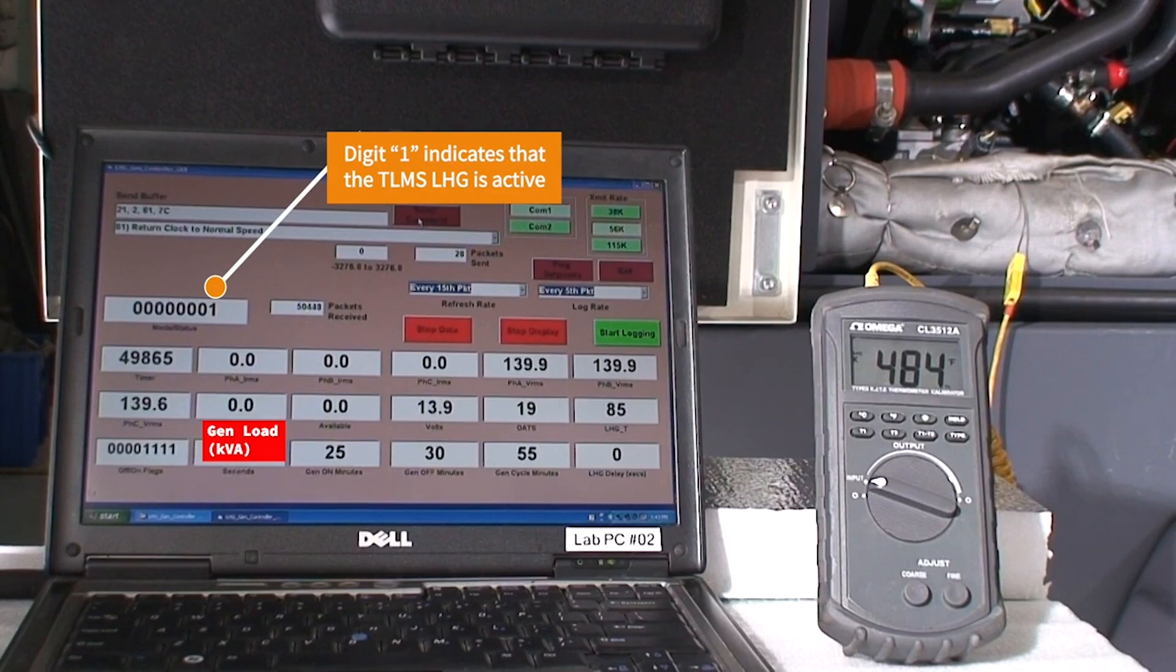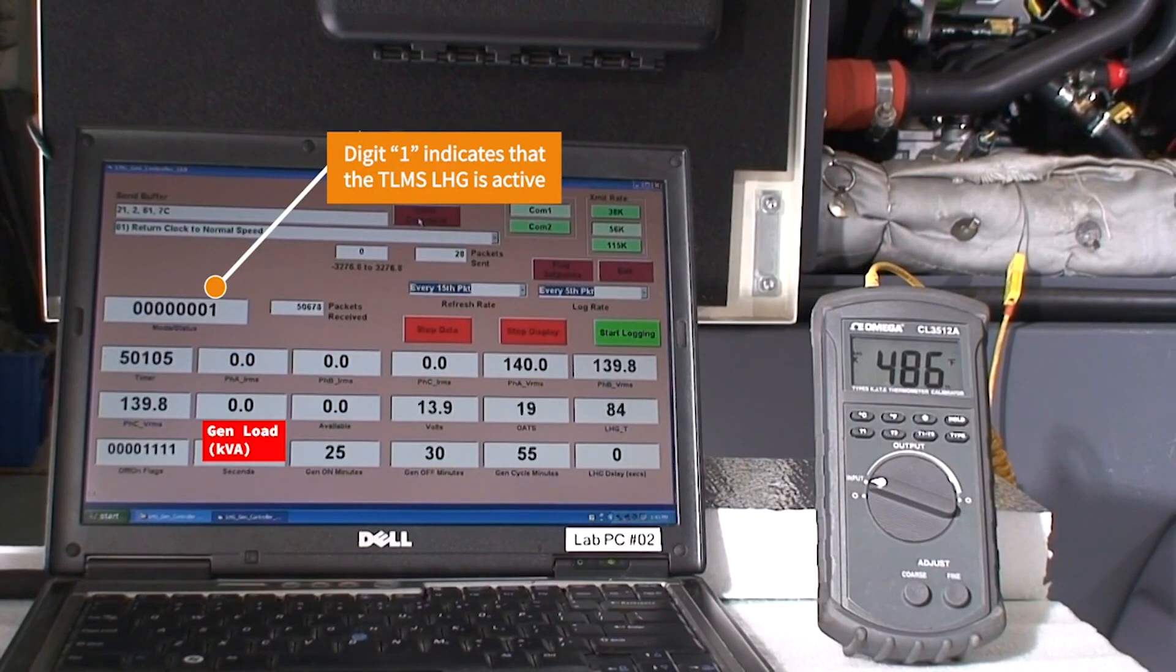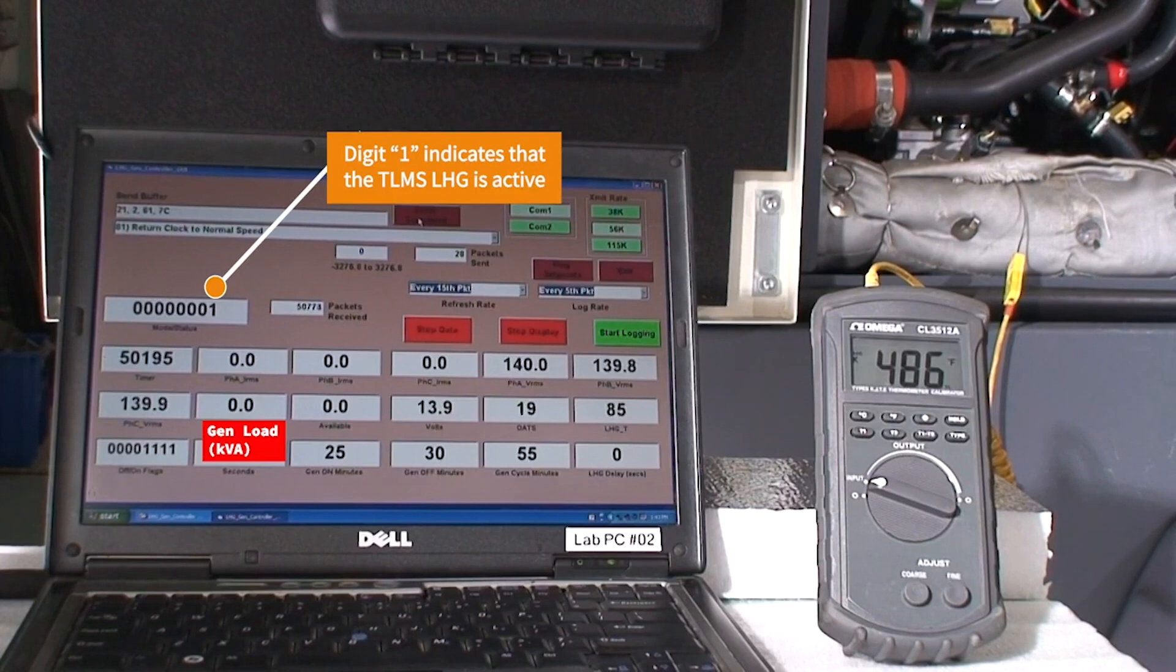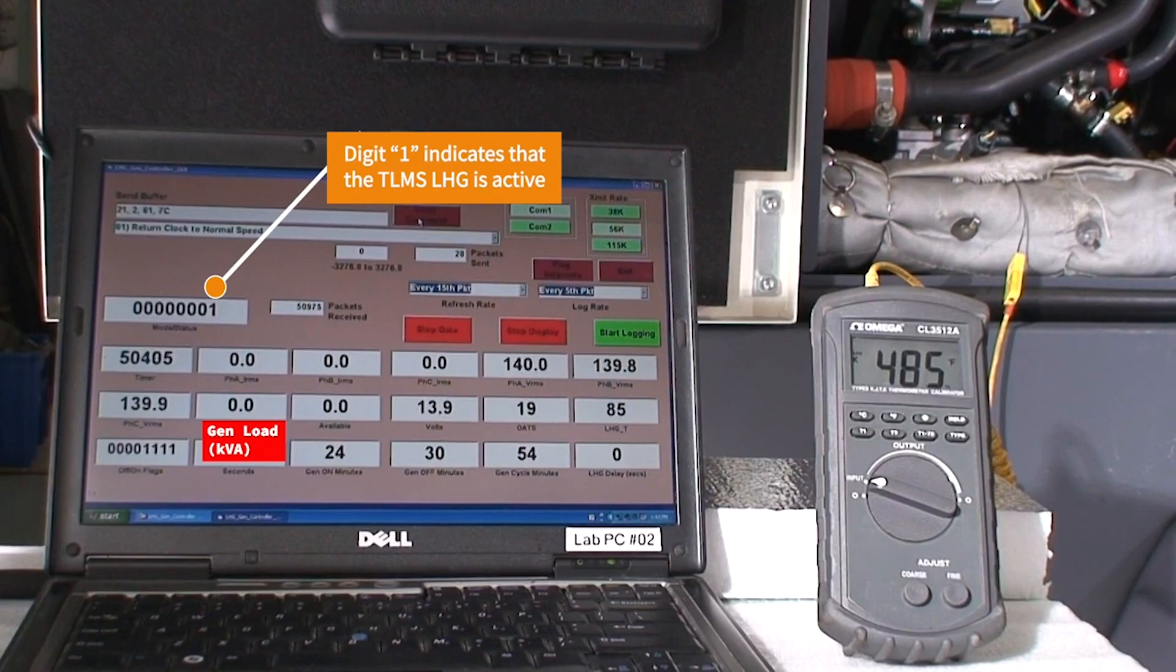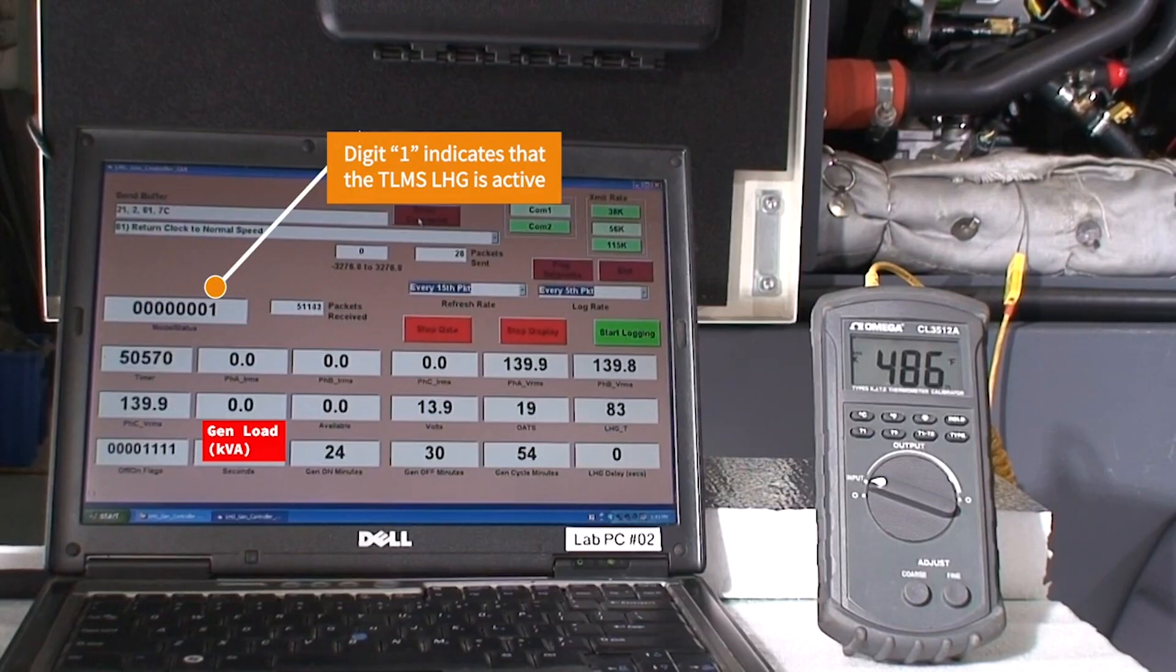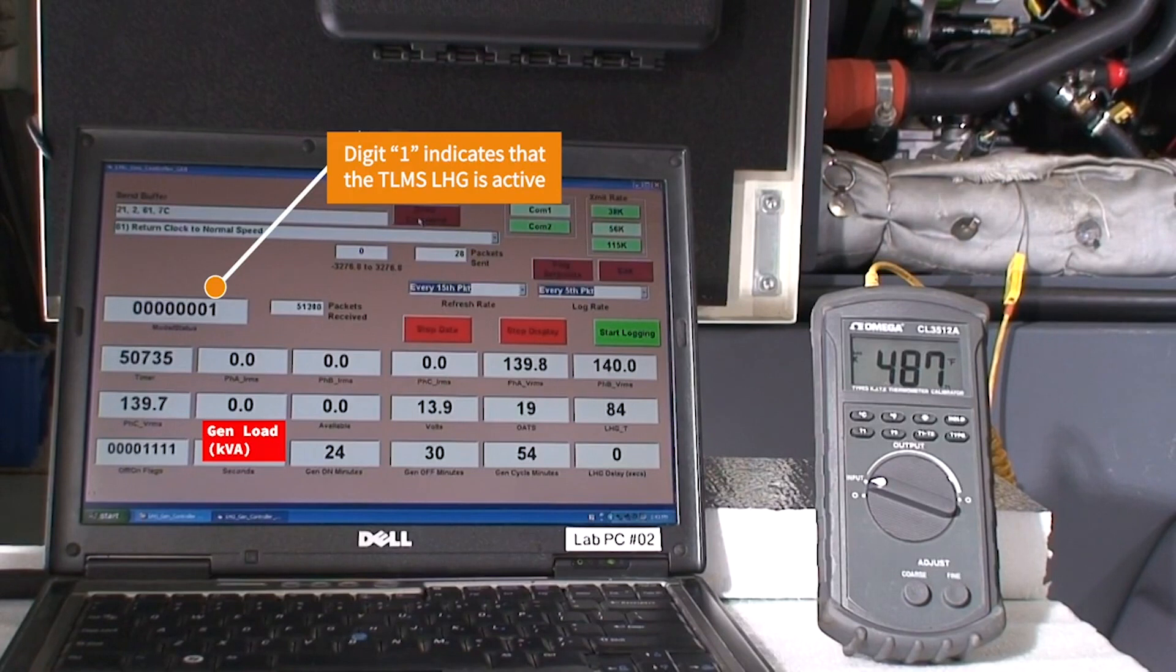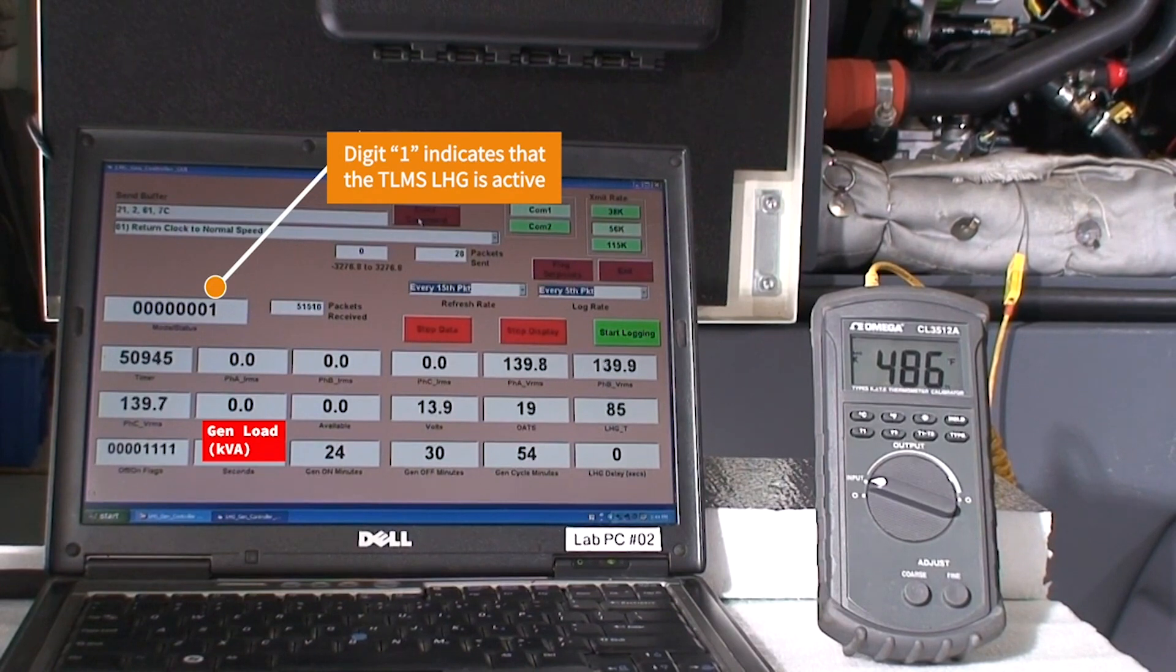In a few moments we will apply 10 kilowatts of electrical load using the load bank. The load will be displayed on the screen where it says gen load in KVA. Instantaneously when the load bank is turned on, the LHG will automatically disconnect. The LHG control system has current measurement transformers which are calculating the electrical load on the generator, causing the LHG to respond accordingly whenever electrical load is applied.